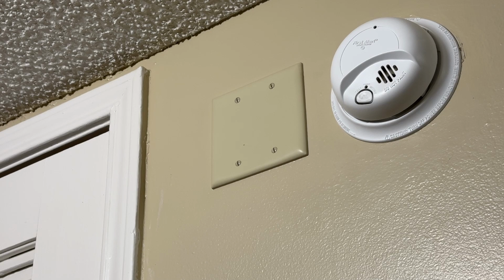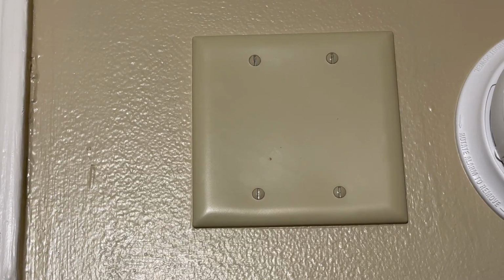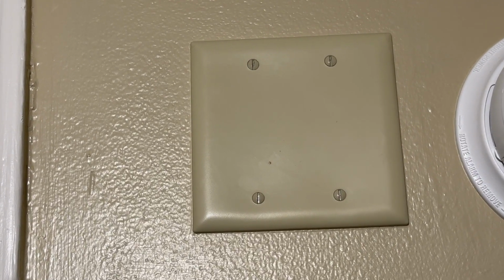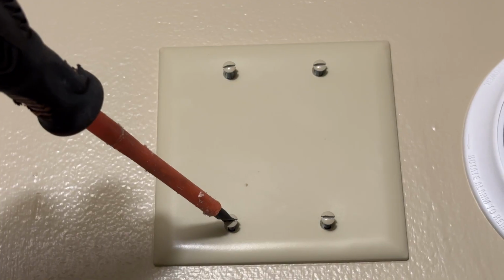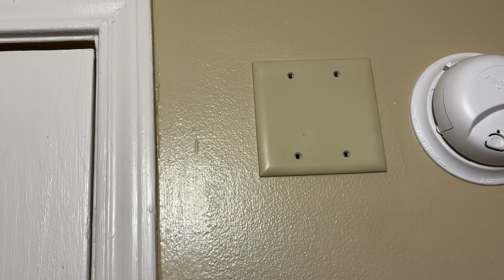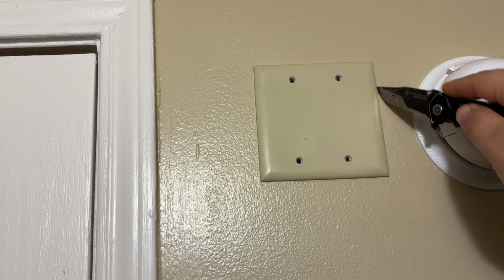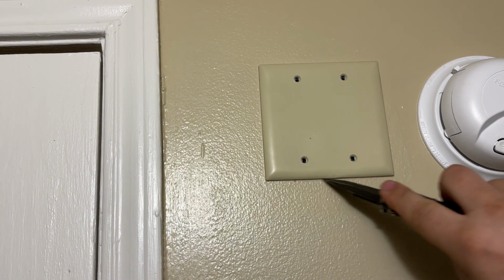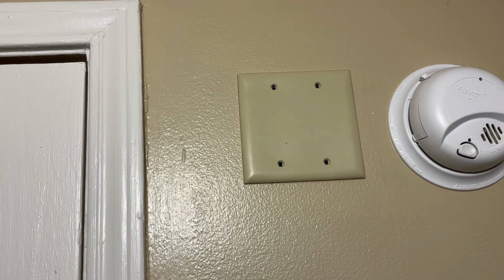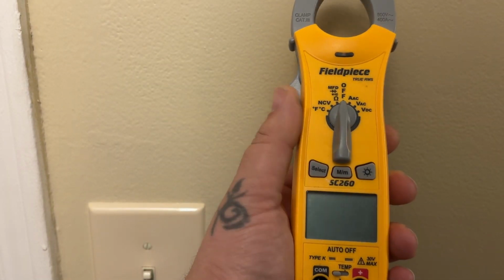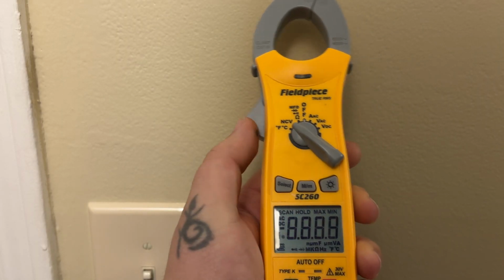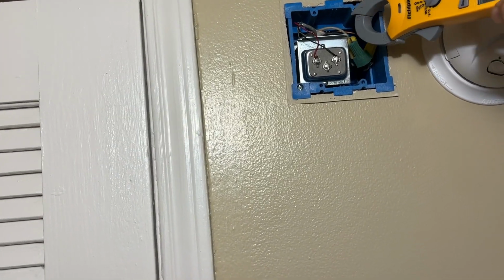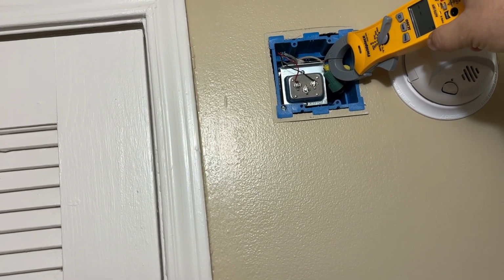When the transformer is located in the hallway, there will usually be a double gang blank close to the ceiling. We will remove the 4 screws and then remove the cover. After removing the screws and before pulling the cover off, take your knife and score around the edges. This will keep the paint from pulling off with the cover. Get your meter and set it to NCV, non-contact voltage. With the cover removed, use your meter and touch your main lines coming in, not your small low volt wires.